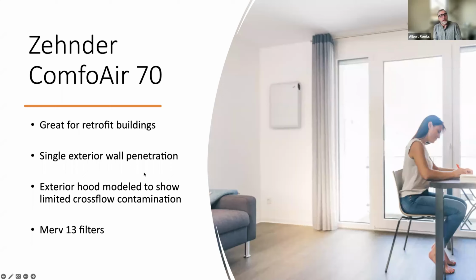So this is a little Zehnder ComfoAir 70. This is a retrofit device. It gets used in new construction, but it's really made for retrofit. It hangs on the wall, and it's designed to serve just a localized little area. On the left-hand side, it's pulling air in. On the right-hand side, you see that black circle. It's supplying air to that location. It's just 1 hole through the wall, and that connects with the outdoors, and it's got filters on board. It's an ERV, so we don't need to run a condensate drain. And in those low airflows, an ERV makes sense. It's got MERV 13 filters, so it checks all the equipment boxes of what we're trying to do.